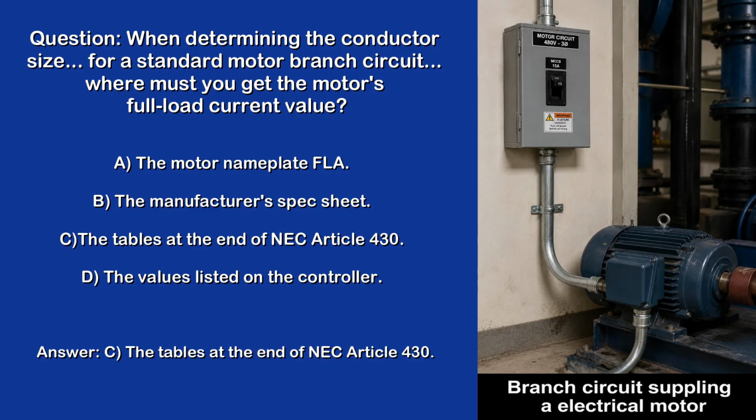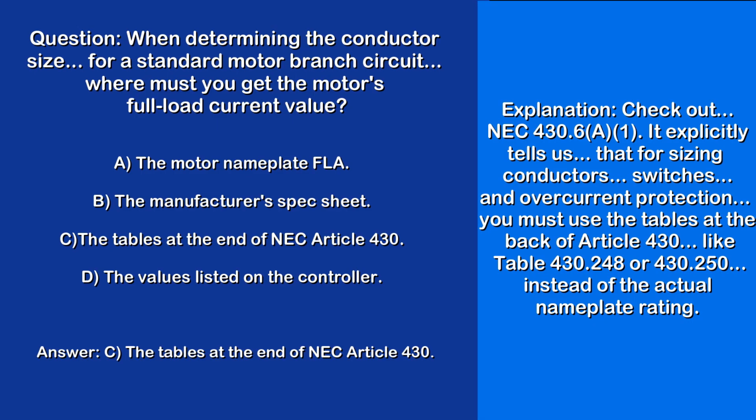Answer. C. The tables at the end of NEC Article 430. Explanation. Check out NEC 430.6, A1. It explicitly tells us that for sizing conductors, switches, and overcurrent protection, you must use the tables at the back of Article 430, like Table 430.248.